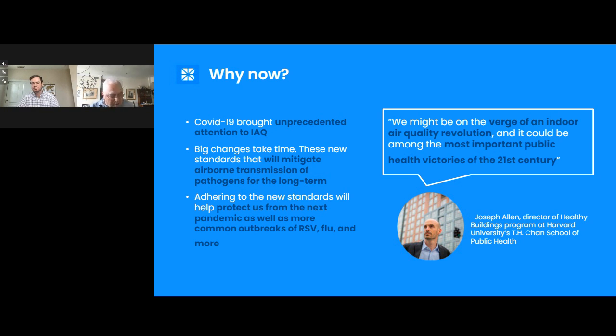It's been gratifying to see this interest now in ventilation, filtration, air disinfection, and airborne infection. In the past, there was a consensus among engineers that a 'healthy' building was one with good ventilation as defined by ASHRAE for comfort - reducing odor, removing CO2, providing oxygen, and handling humidity, cooling, or heating. All of that can be done with relatively modest ventilation, and that's what most systems are designed for.